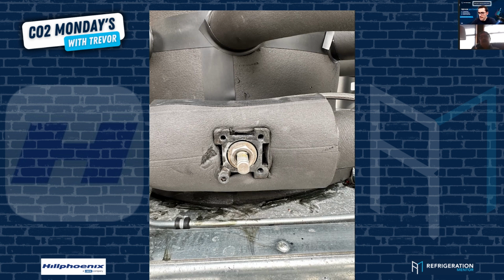Basically, you've got to determine which it is, if it's the heat reclaim inlet/outlet or the condenser outlet/inlet. Determine which one it is. You can remove the lock, the little bead lock in there, you just punch it out and you rotate the valve 180 degrees, put the lock back in, and that'll 99% of the time take care of your blow-by problem. Excellent.